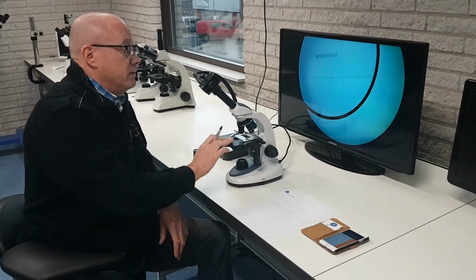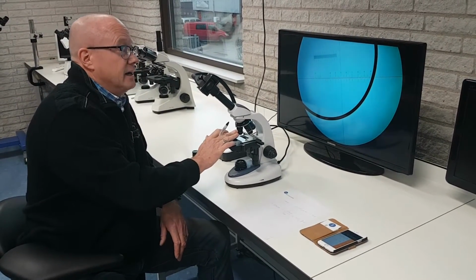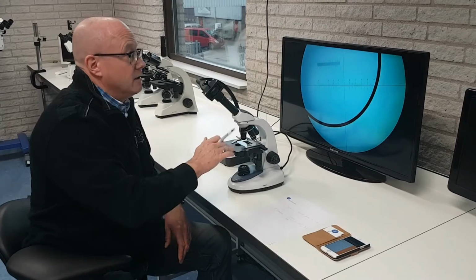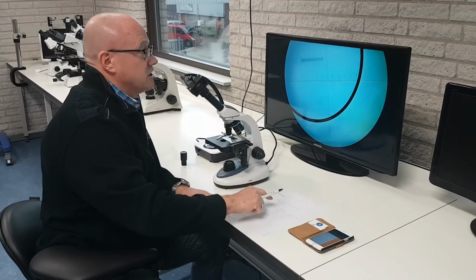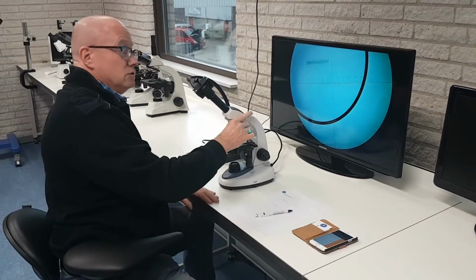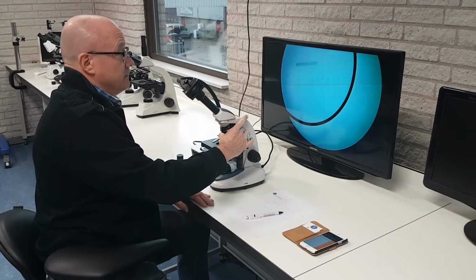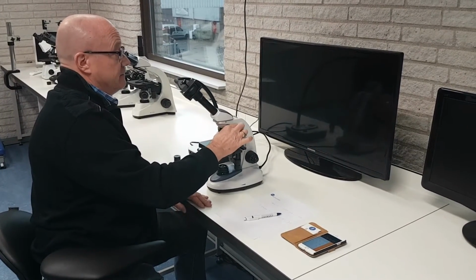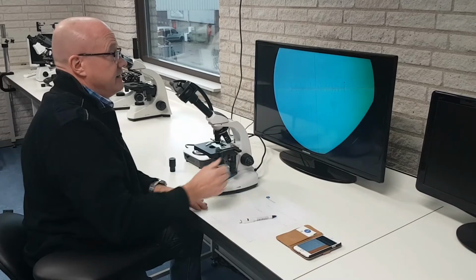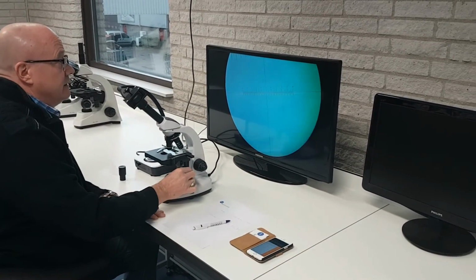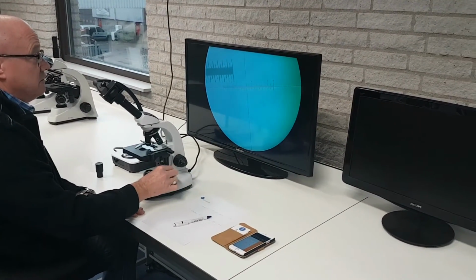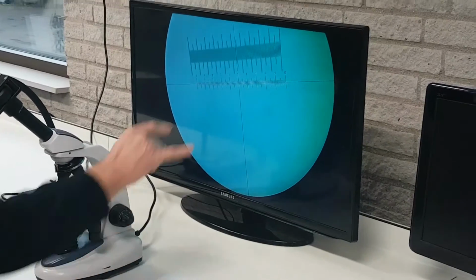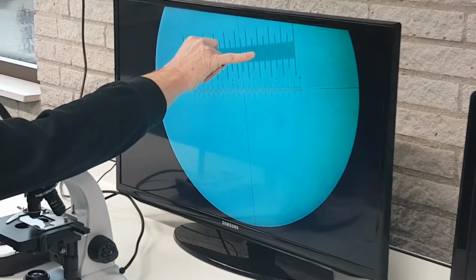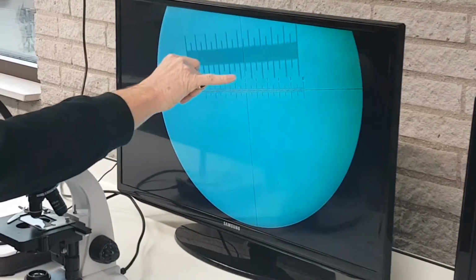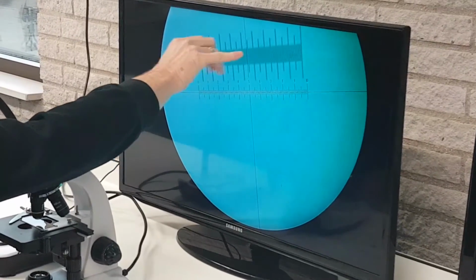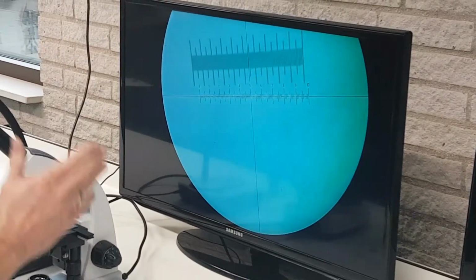This microscope with the 4x objective is now calibrated. For each microscope objective I need to repeat this calibration again. This is the 10x objective, and if I put the stage micrometer on top, you can see this is still the same stage micrometer. It's still the same 1,000 micrometers, only it looks bigger, but it's still the same.